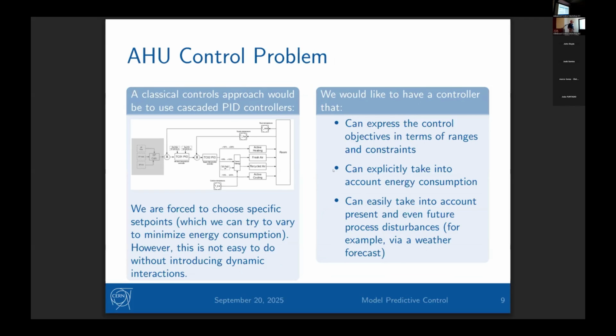Classically you'd solve this with something like a cascaded PID. When you do this, you're treating it as a regulation problem, so you have to choose set points, and the optimization you can do is restricted to setting those set points. If you do this dynamically too much, you can get odd dynamic effects in your closed-loop system.